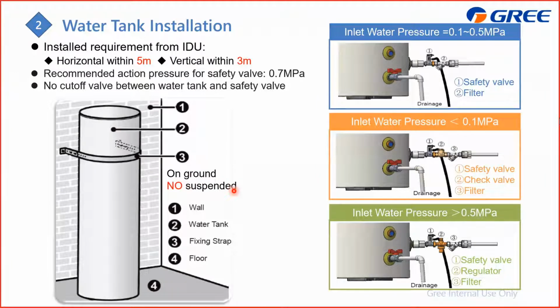And also for the inlet water pressure, we require from 0.1 to 0.5 megapascal. And if your local water pressure is less than this, you need to install like this, which is to add a check valve. And if your local water pressure is higher than 0.5 megapascal, you also need to add a regulator to lower the pressure into the water system.